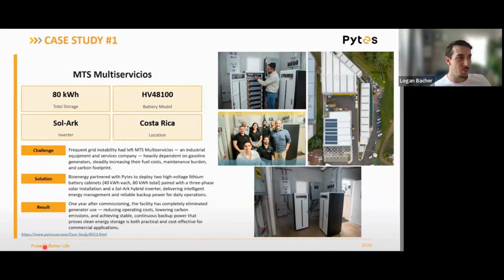This is actually a really good point. When we do these high voltage systems, we do not recommend installing them in open loop. Open loop means there's no communication between the batteries and the inverter. That method without communications is maybe not so widely used these days, but it's definitely still widely acceptable in the residential world where we're using low voltage batteries.